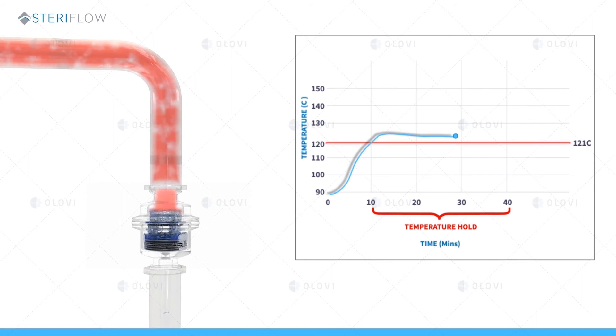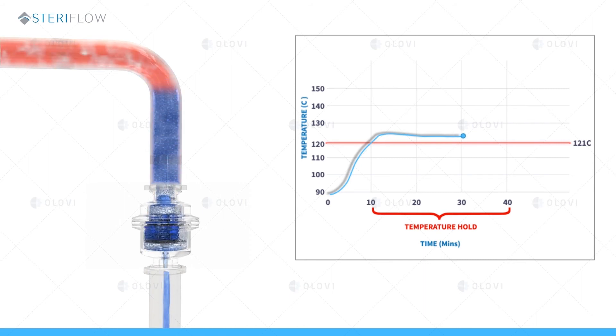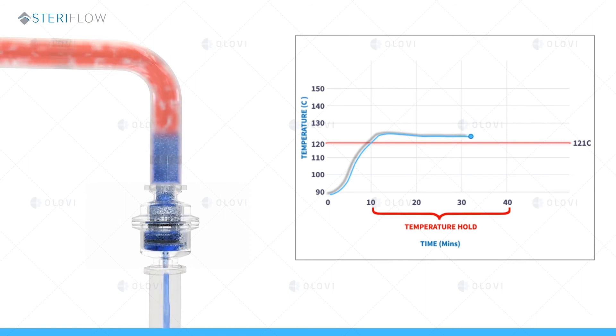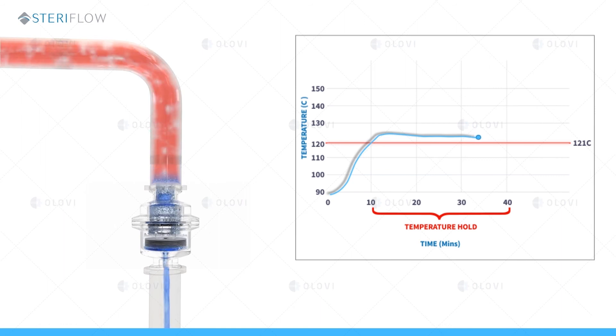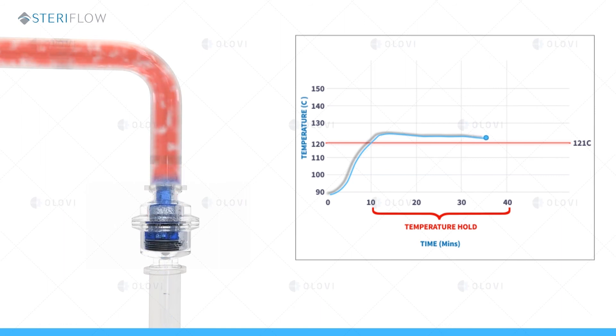A well-designed trap will open when the condensate temperature is just a couple of degrees below the steam saturation temperature and won't allow the condensate to rise to the level of the temperature sensor.